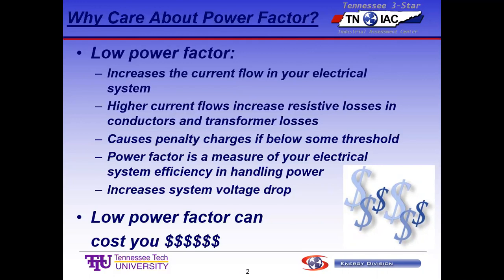Okay, well why do we care about low power factor? We get into the engineering of it a little bit here, but as power factor drops, the current flow required by the electrical system increases. The power doesn't necessarily increase, but the current draw increases. And that current draw is current that the power company cannot sell to another customer. So you are reducing their opportunity to make money off of their generation by screwing up your power factor, and we're going to get you for it.